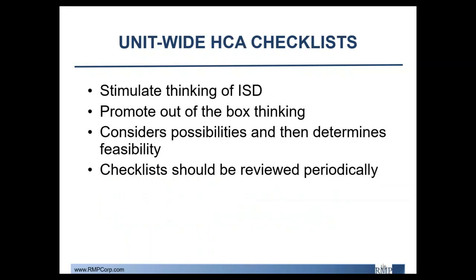HCA checklists can be added at the end of HAZOP studies to stimulate thinking of inherent safety review for the overall plant or unit. Checklists are intended to promote out-of-the-box thinking and generate ideas that might be usable in an existing facility or one planned for the future. They should not be used in a rote yes-or-no manner, but rather to consider what might be possible and then determine what is feasible. Checklists should be reviewed periodically throughout the life cycle of the process — California refineries are required to review this checklist every five years — because as technology changes, what was once infeasible becomes feasible.